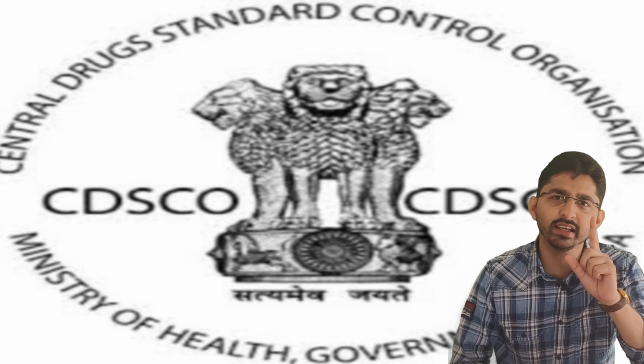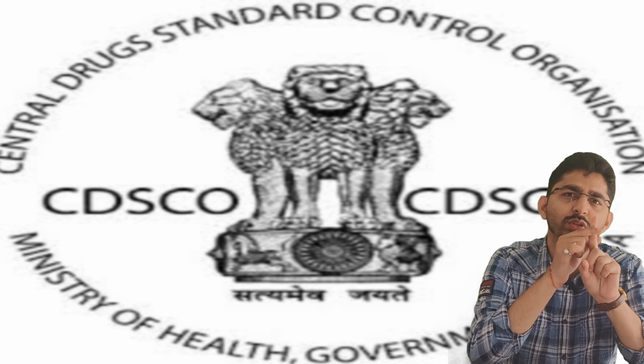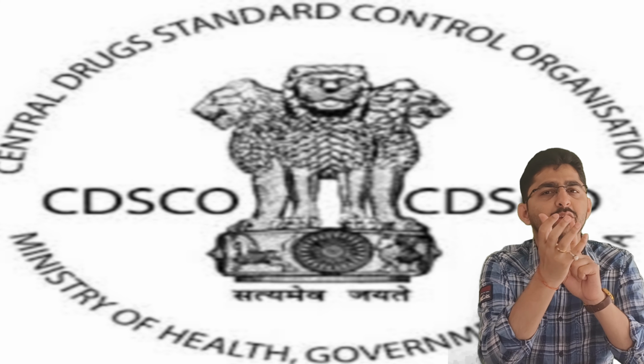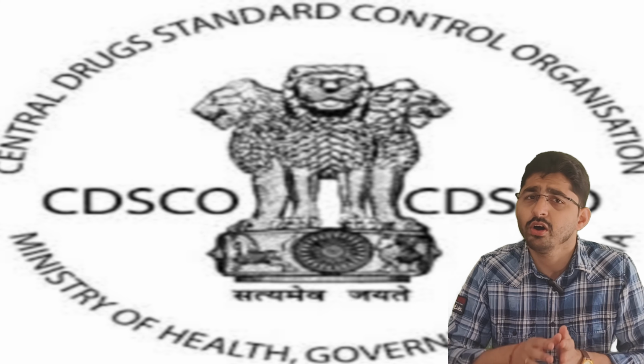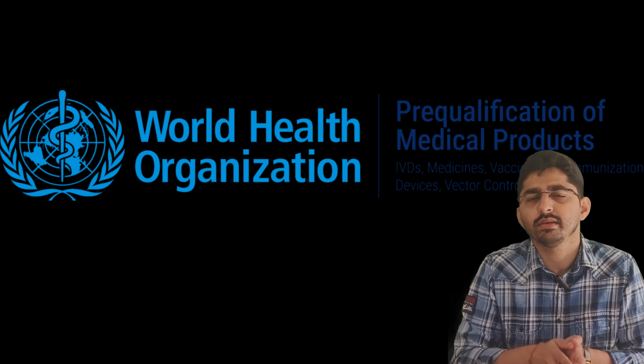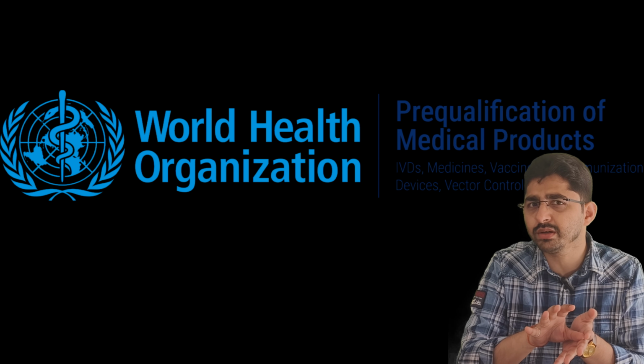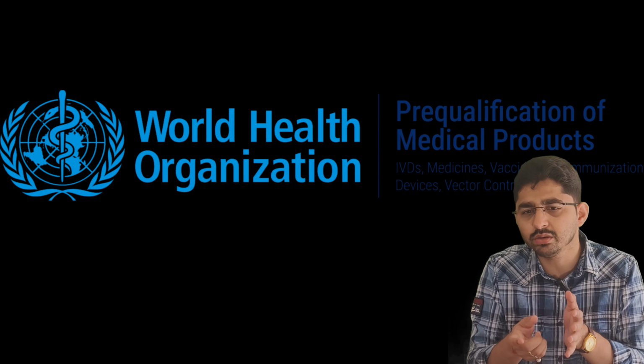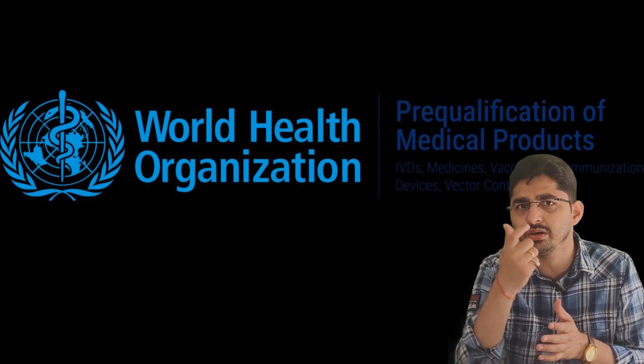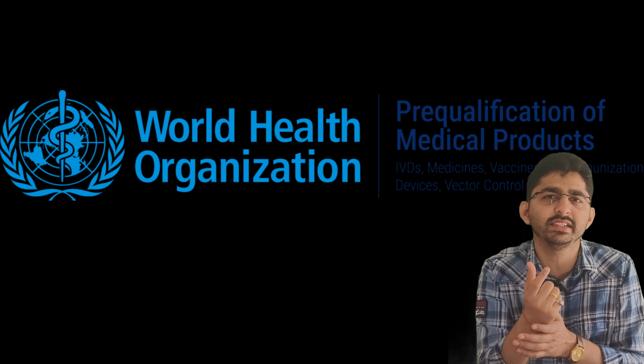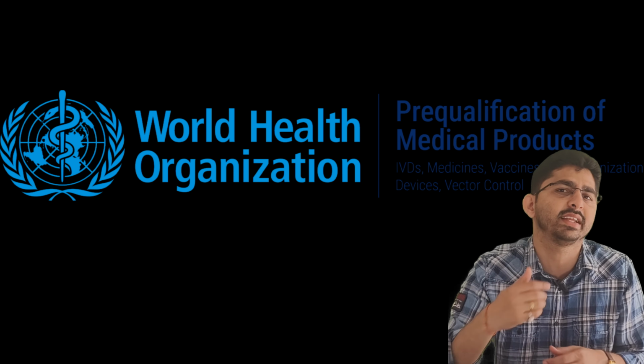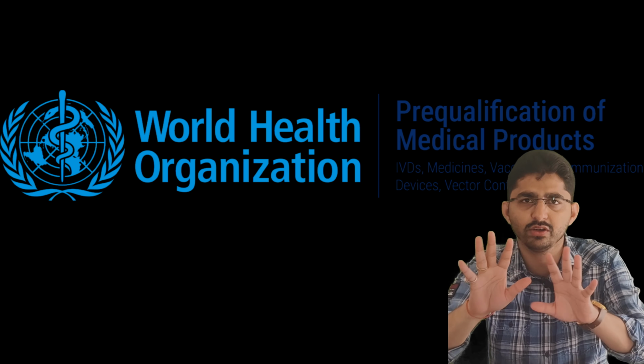So these 3 stakeholders, my friends, were for the case of a medical device which is not PQ compliant, right? If my medical device is PQ compliant, then the WHO, the organization, the WHO technical committee, will be added as the 4th stakeholder, right? So I hope it's clear.